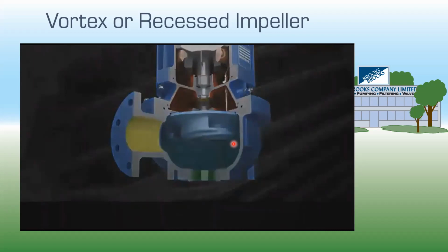Now, Chris, what do you think the negative is here? There's always a negative. I suspect the efficiency would be a problem with this pump. Yeah, you're right. Efficiency is going to be in that 30 to 40% range. So nothing's free in life. And again, this is just another way of moving fluids. Not all fluids are clean water.